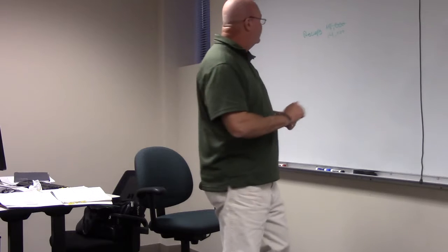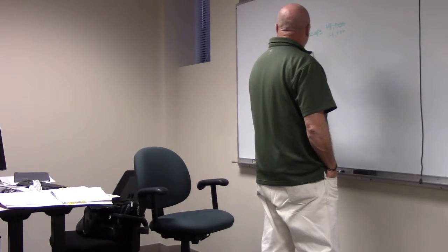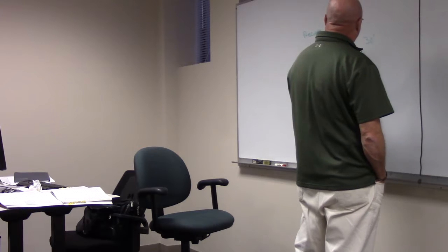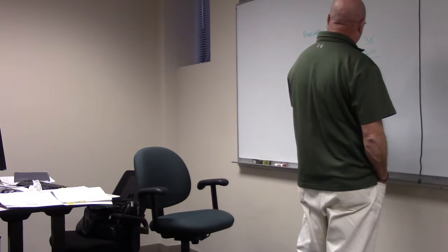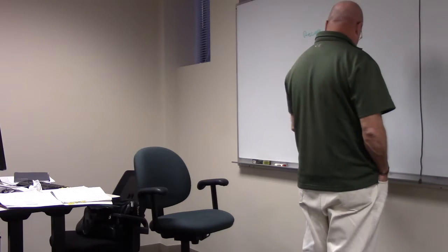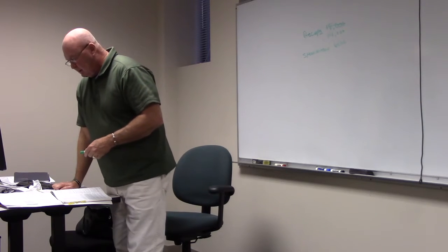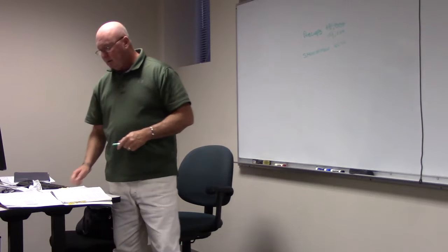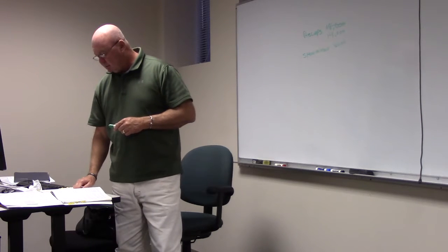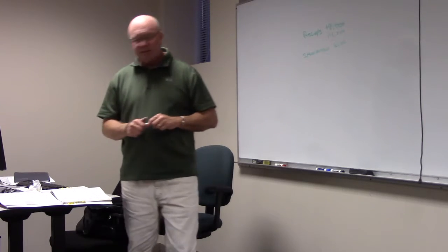Step 3, we got a show window. How many feet? 30, times 200 VA, is 6,000. Leave that there for now. Right now we're doing the 208 volt stuff. Incandescent lighting is part of that. They told us they had 75, at 150 watts each. How much does that give us?